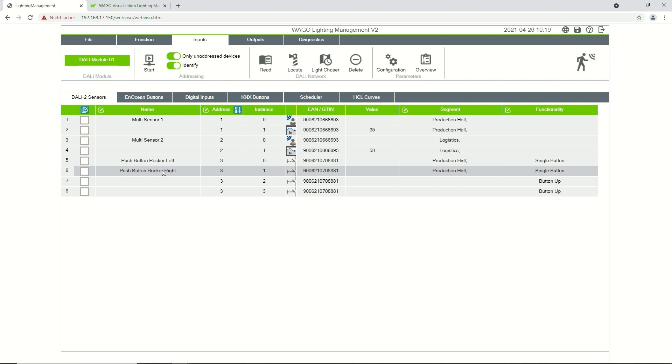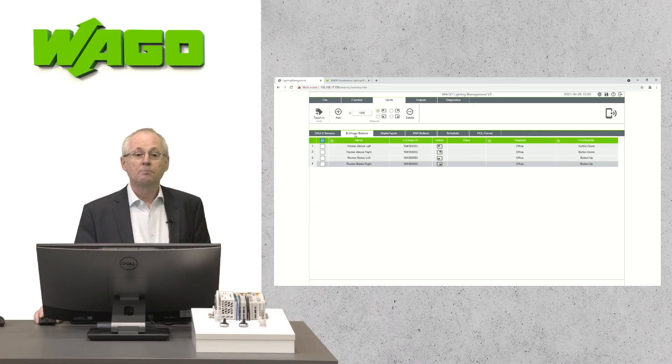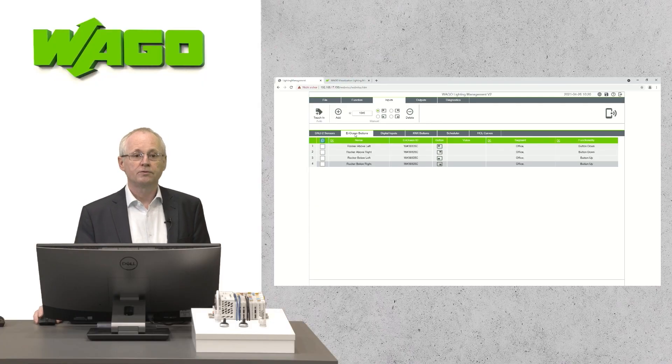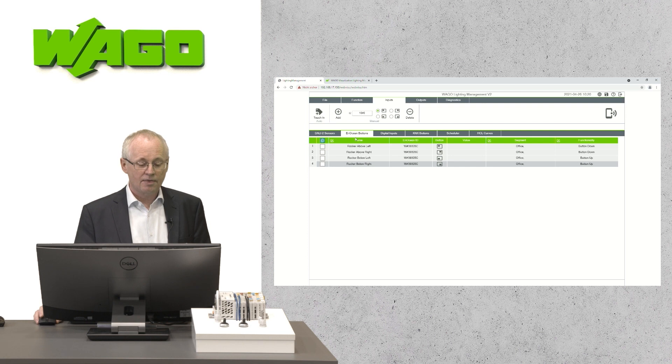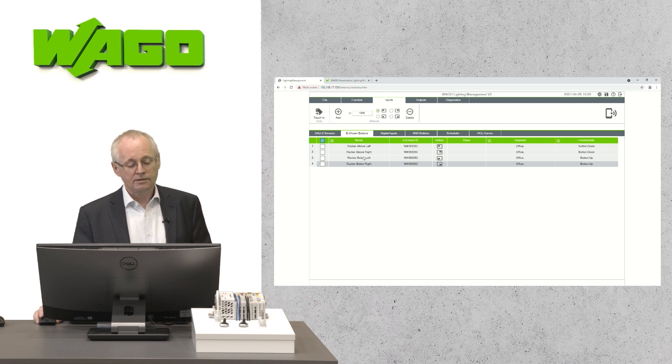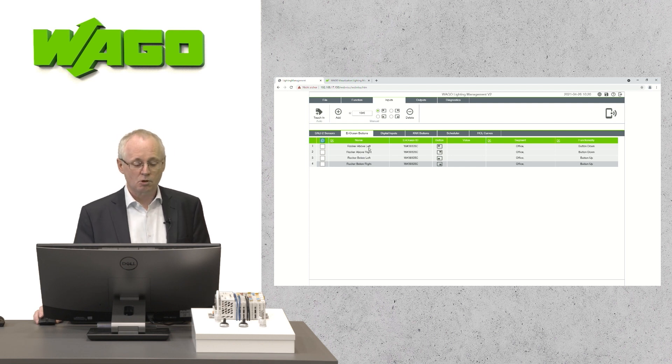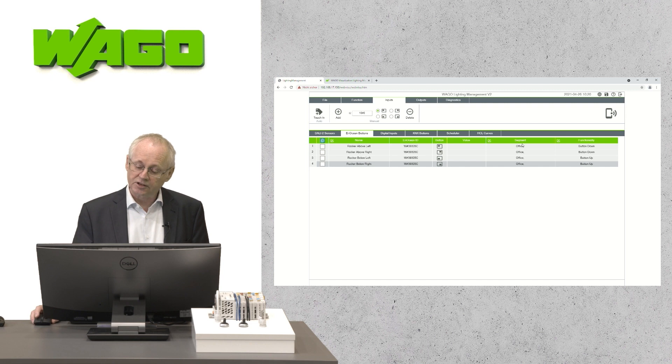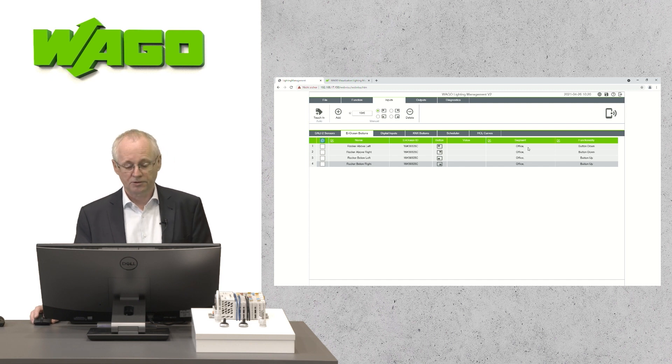In case of a new configuration, you could start the addressing and all sensors which are connected to the DALI line will appear in this list. After that, you can give each sensor a name and you can assign the sensor to a segment. The application supports also EnOcean wireless. You see there is already one device configured with four rockers. You can again assign a name to each rocker and assign each rocker to a segment.